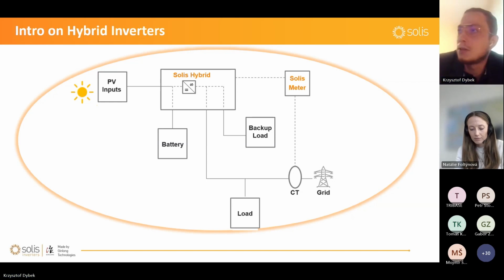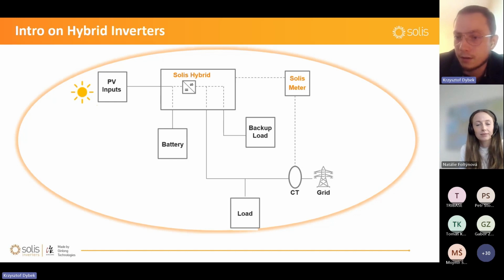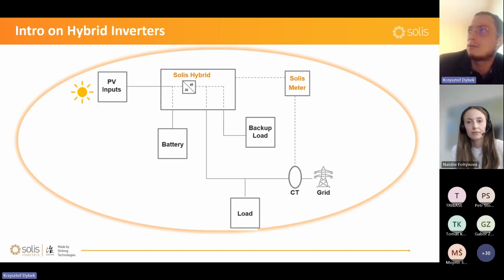So what we need in hybrid system, except the inverter, is the battery here and the meter, of course. Yeah. So meter is constantly sending signals to the inverter. If it detects that your load is not covered by PV and wants to import energy from the grid, immediately it will tell this information to the inverter. Inverter, within 1 second, starts to discharge battery to cover the load. So your import will include only situations when both PV and battery can't cover the load.